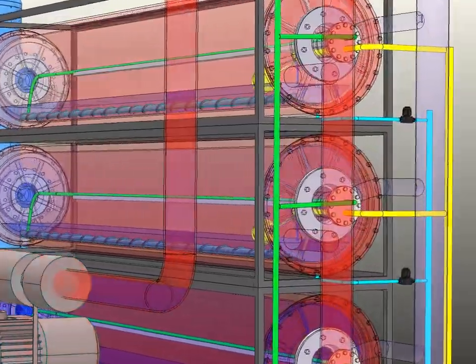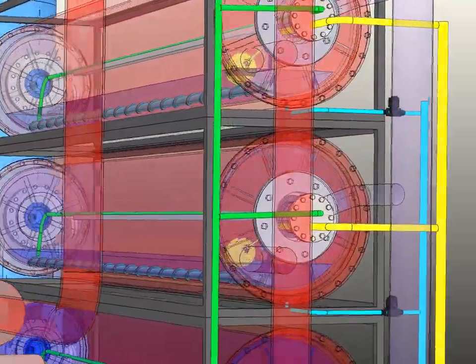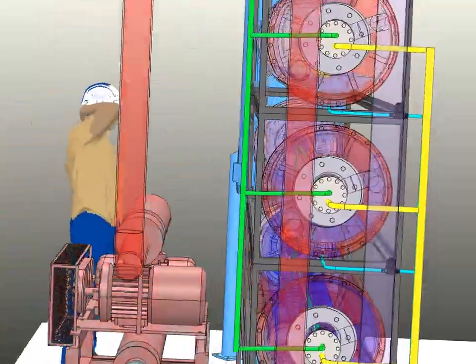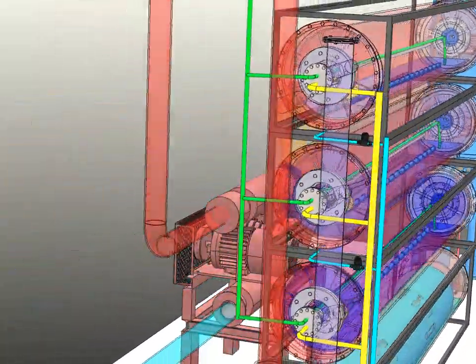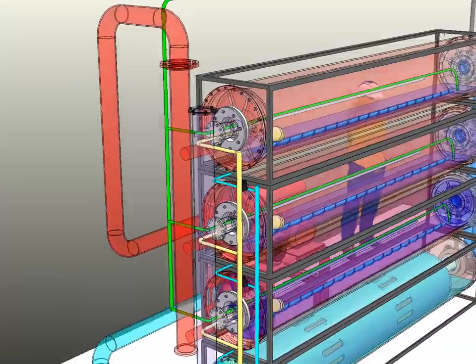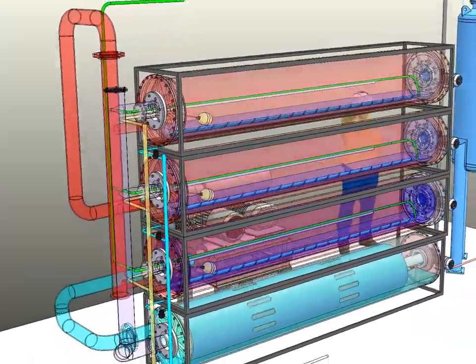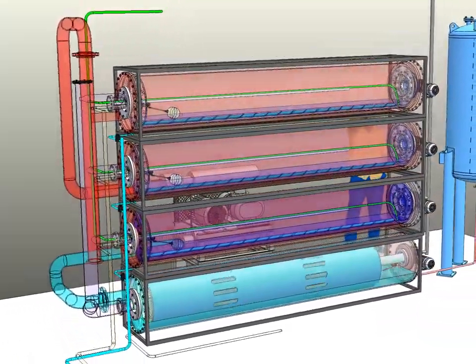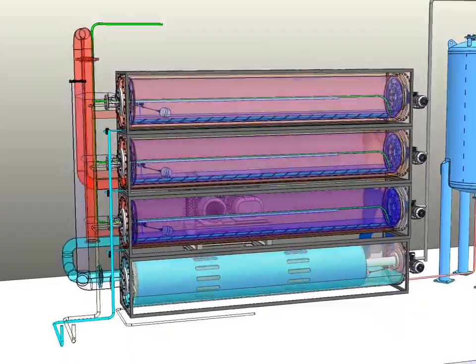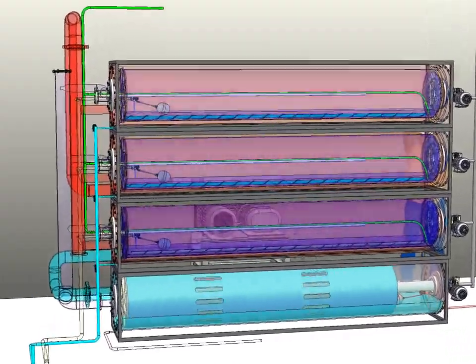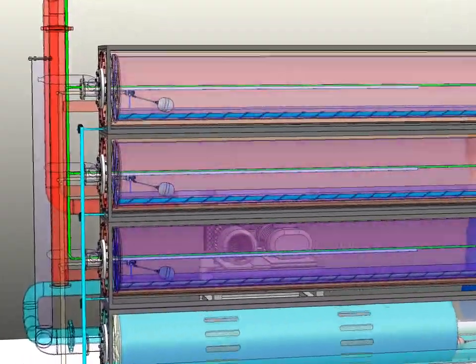In the example shown, a roots pump of 500 kg/h compresses secondary steam at a pressure of 70 kPa to 140 kPa and raises its saturation temperature from 90 to 109 degrees Celsius. This allows to use this steam as heating steam in a DFE.